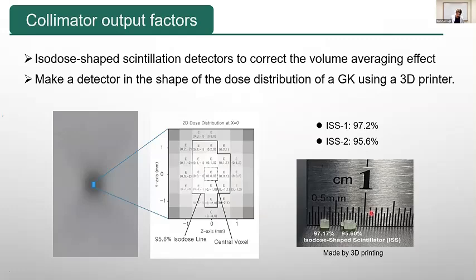So the most intrinsic problem in small field dosimetry is that the dose distribution is not flat inside the detector. So the measured value is always smaller than the dose rate at the maximum point, and we call this the volume averaging effect. To account for the volume averaging effect, we developed a very interesting scintillating detector shaped just like the dose distribution. So we can calculate the volume averaging effect very easily, just add and divide. And this one is the actual scintillator. It looks something like a cube.